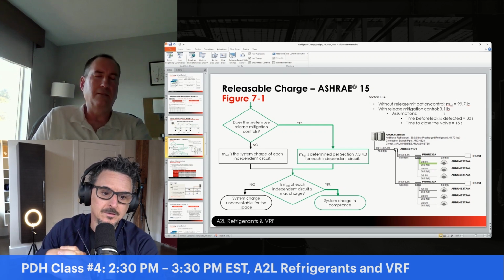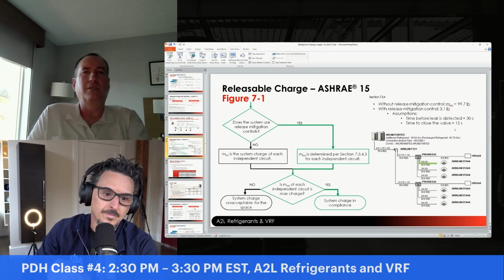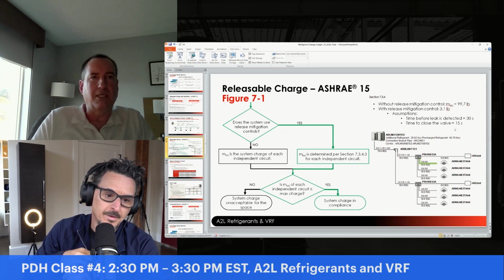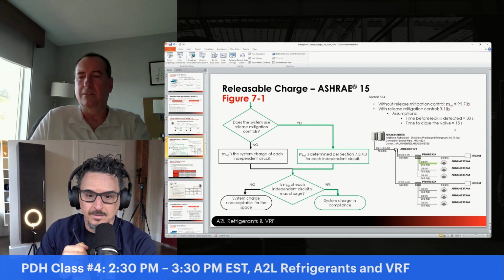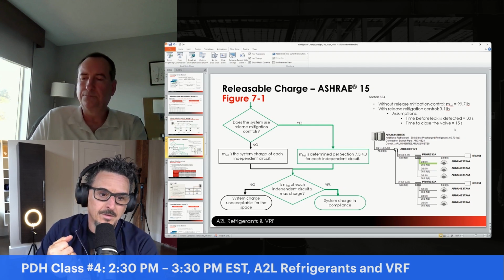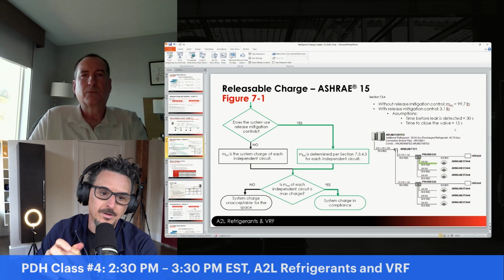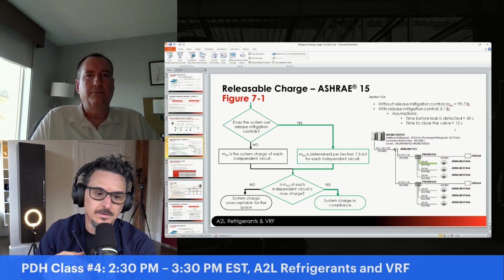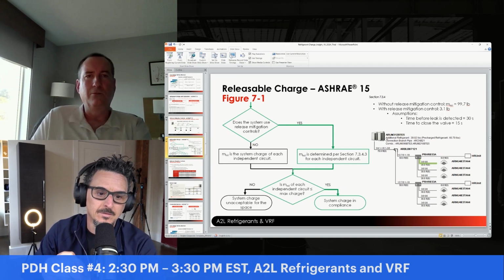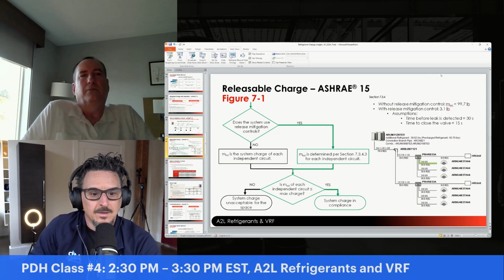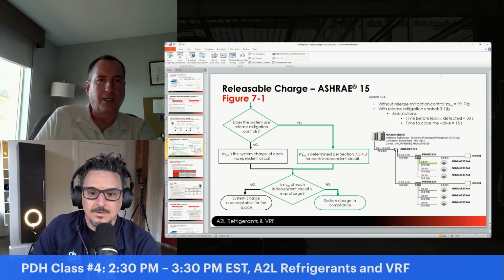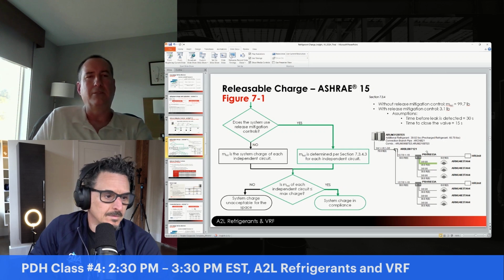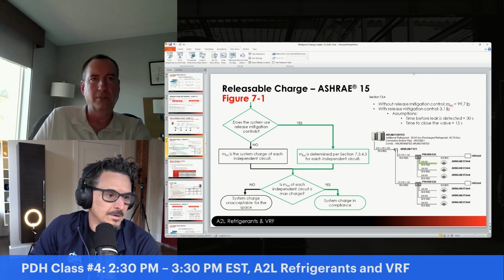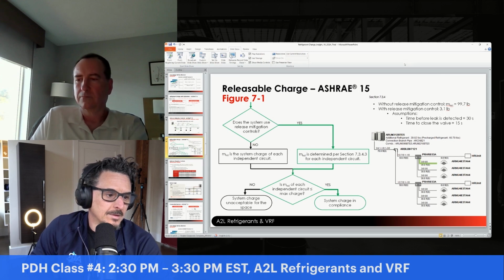Wow, this is a huge difference. A huge difference. Yeah. So this is assuming that it takes about 30 seconds to detect the leak and about 15 seconds to then close the valves. So 100 pounds. What? Oh, that's the concentration limit. Okay. Got it. Yeah. That's like the max. Looks like we got 100 feet of pipe out to these HRUs and then more piping beyond that. So a decent sized system, I guess. But yeah, this difference is huge in those two numbers.